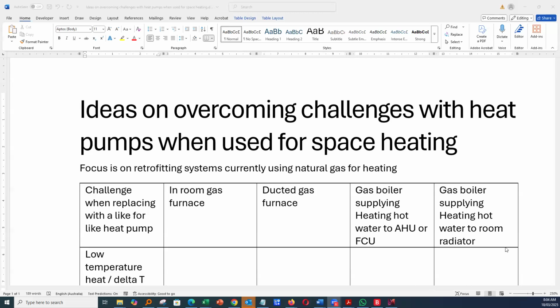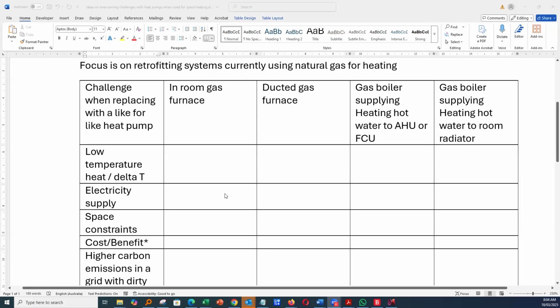Now, it won't necessarily be a problem when the load is light on the system, but when you've got a heavy heating load, then it's going to be a problem. Okay, electricity supply. Yes, if you put in a split system, it's always going to use more electricity than the fan on a furnace, or the burner and pumps associated with a boiler, and any fans. So yes, you're going to need more electricity. Possibly, depending on the extent of the upgrade, you need to upgrade the electricity supply. So that could be a problem. Typically, when you're replacing large boilers, that is definitely a problem, and the electricity supply will need to be upgraded. So that's a challenge for all systems.